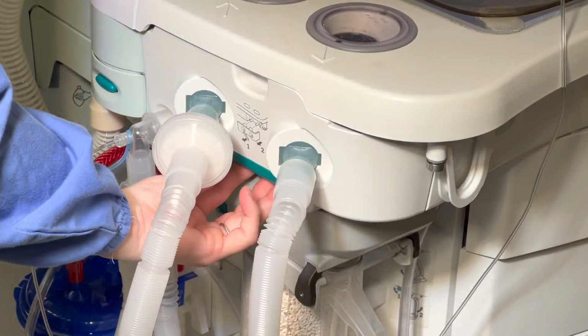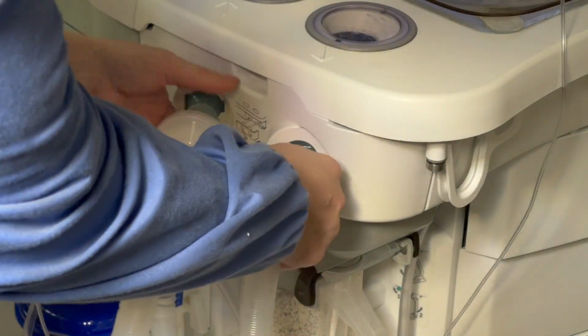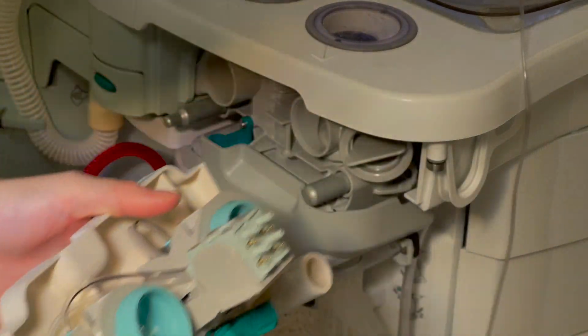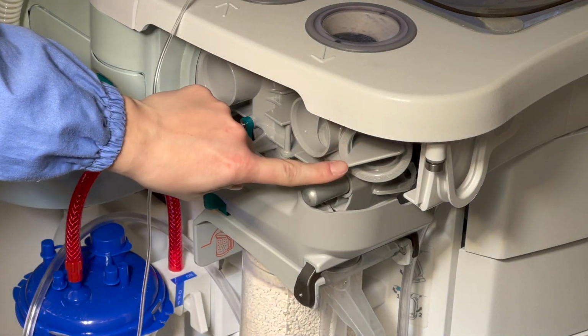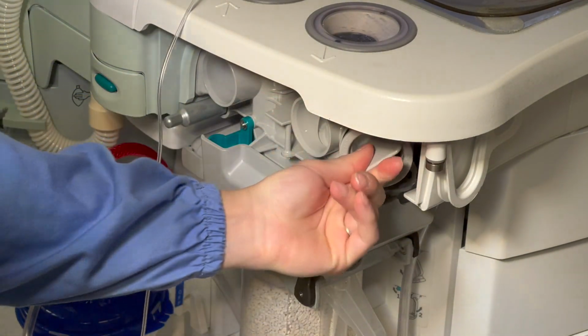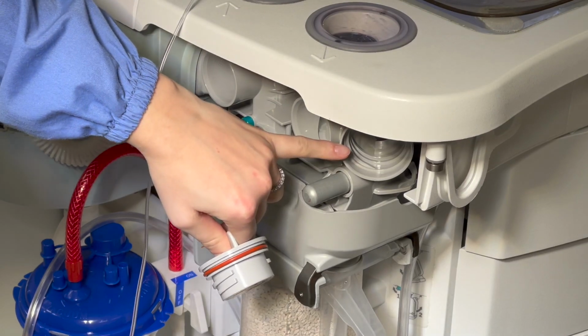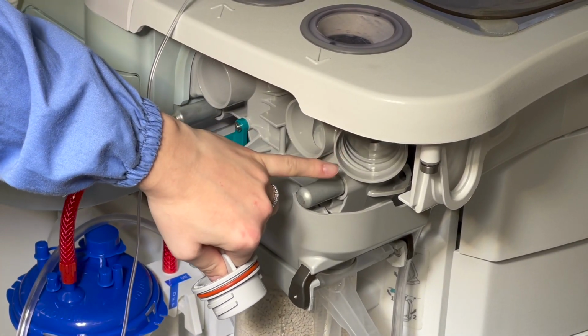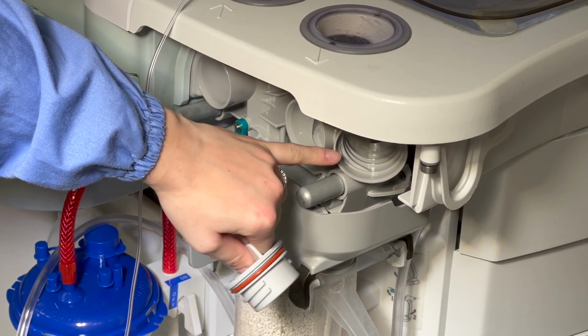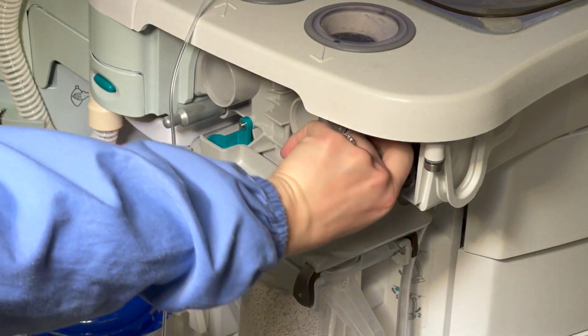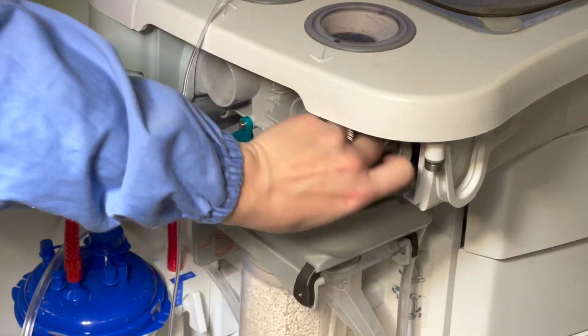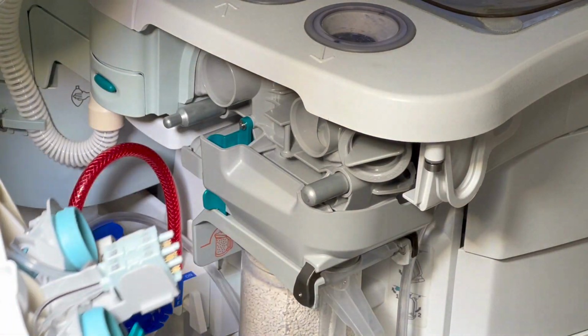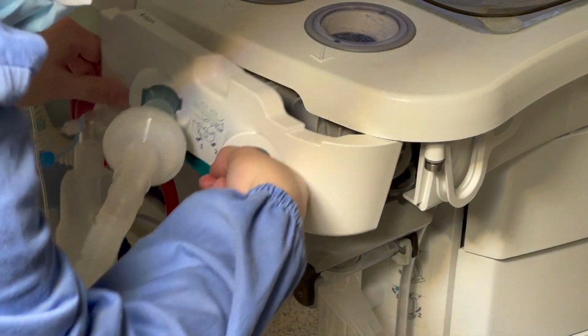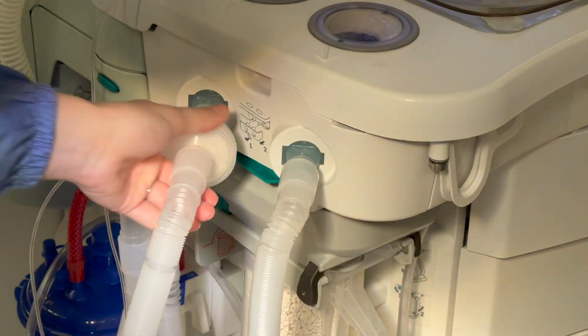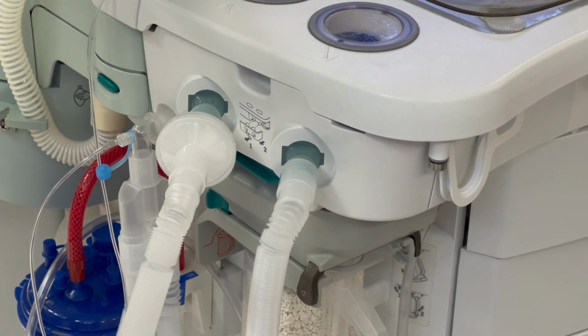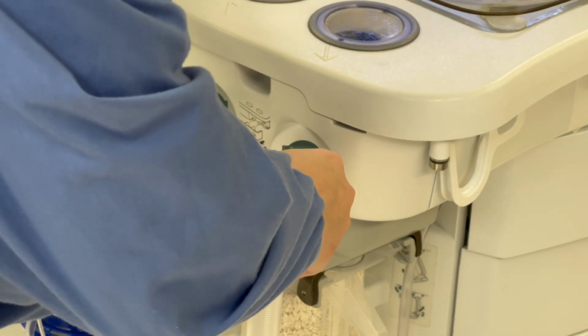to room air. Next, you'll want to remove this latch here to expose the flow sensors and also the O2 sensor. Some models don't have an exposable O2 sensor, they have an integrated one, so you won't need to expose this, but go ahead and do it anyways just to be thorough. And be very careful as you're putting this back in. Most people don't take it out this far, but we're doing it now just to show you what's inside. And then go ahead and reinsert the latch.